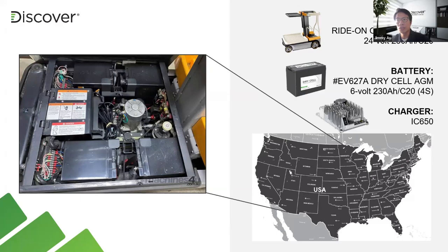If it's required to be used and discharged down all the way to, let's say, 80 to 100% DOD, or what we call depth of discharge, lithium again could be a good fit, because within the same form factor that you see here, lithium can pack in more capacity or runtime. It's also able to deliver, with the proper BMS in these lithium batteries, a faster charging time, given that there is a higher output charge source in the warehouse. So knowing the charger output and the sources available is important to get the fast charge you need for lithium. Otherwise, it's not that big of an impact.